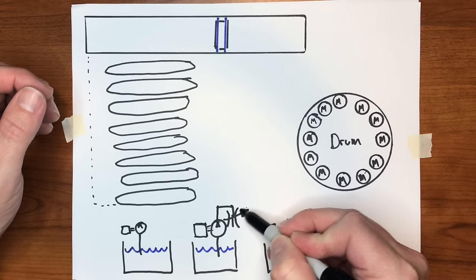One of the things that I didn't touch on back there is... I've done a video on this before. It's on the side of the track. It's that little rail that sits there, and that's a linear transducer. And that guy is necessary to tell the PLC that the launch dog has actually caught the catch car and is not rolling further back. You could do it with proximity sensors, but I bet they want that position to be very exact to where it says, yep, we have fully caught the catch car and it's engaged and nothing else.